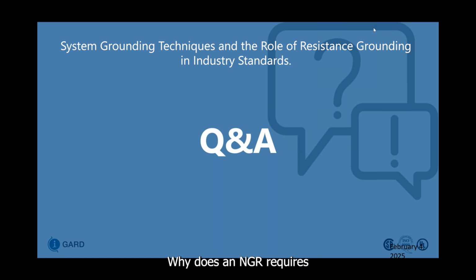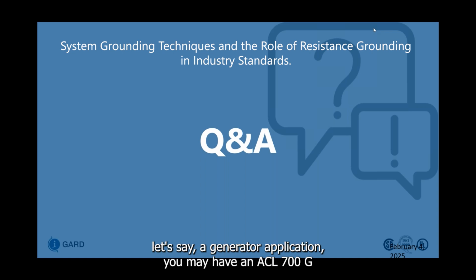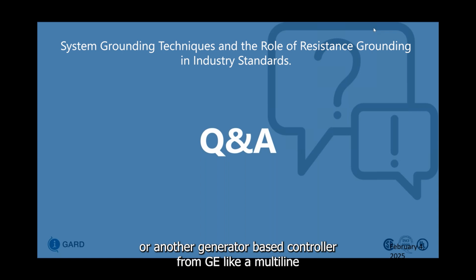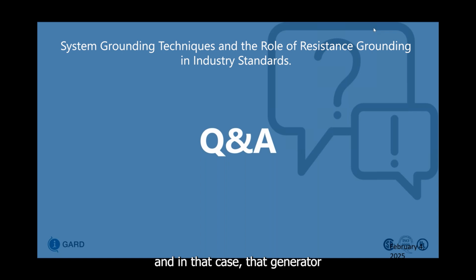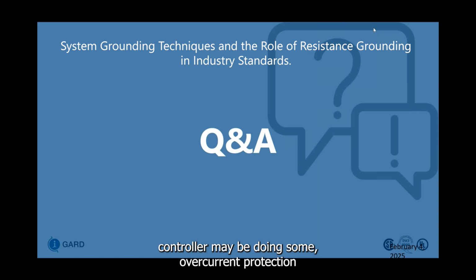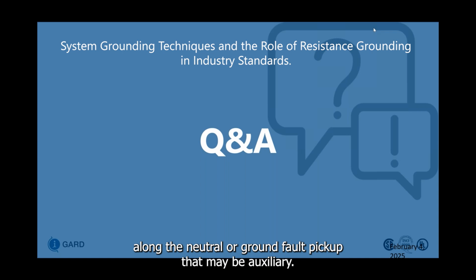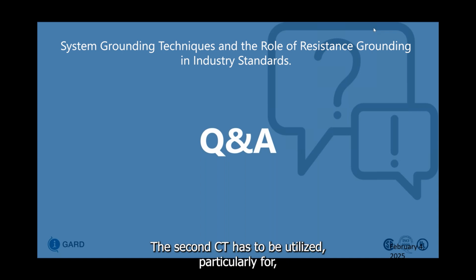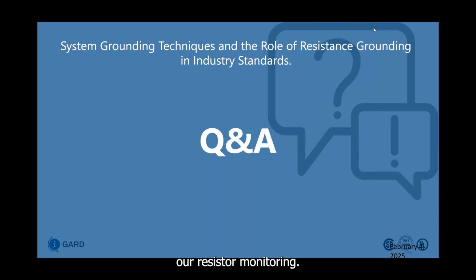Why does an NGR require two sets of CT sensors? Two sets of CT sensors may be required because, let's say, for a generator application, you may have an SEL 700G or another generator-based controller from GE, like a Multilin. And in that case, that generator controller may be doing some overcurrent protection along the neutral or ground fault pickup that may be auxiliary. The second CT has to be utilized particularly for our resistor monitoring.